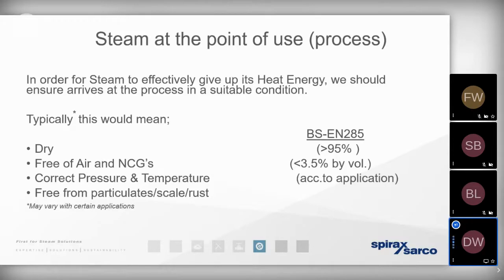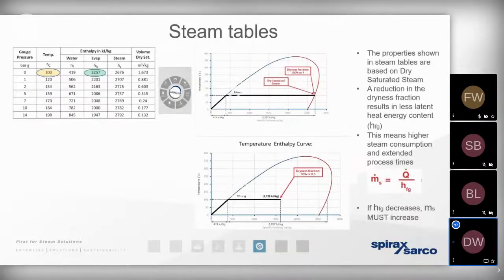But when we're talking about using steam for general purpose, general heat transfer purposes, we really just want to ensure that we're keeping the steam as dry as we possibly can, for the simple reason that the drier the steam is, the more energy is present within it. But we also need to give thought to the air and the other non-condensable gases. If we've got a significant mass of air and other non-condensables entrained within that steam, then we know that there's going to be a barrier to heat exchange. So let's have a look what that actually looks like on the steam tables.